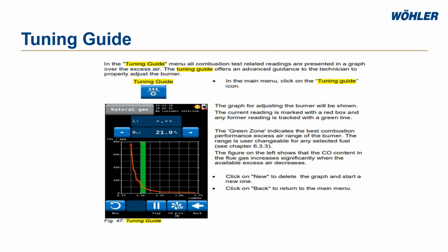Here's the tuning guide, a feature a lot of people don't know about. The best way I describe it: say you're doing a test on a furnace and having a hard time adjusting your carbon monoxide reading, and you've done everything you think you can do - I'd go in and use the tuning guide. You can use it to adjust a gas reading with excess air. That green bar in the graph is what we call the sweet spot, which is essentially where you're trying to get your reading to be.